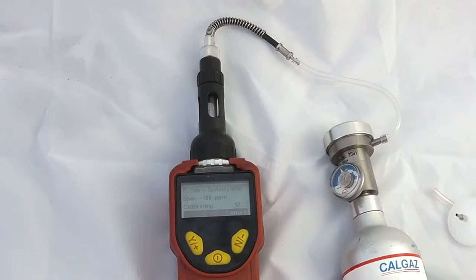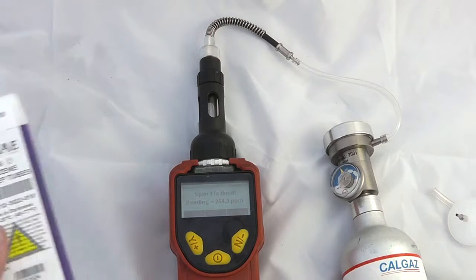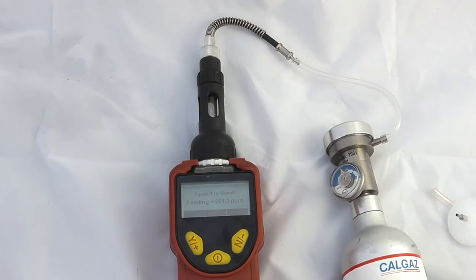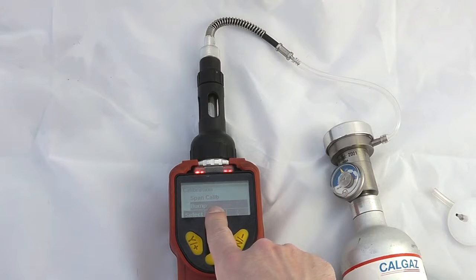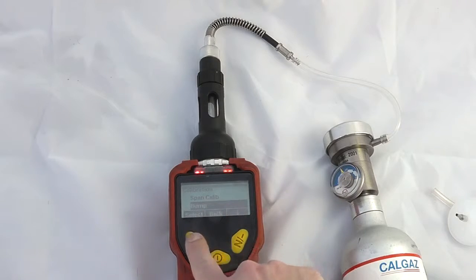At the end of this we should get a positive calibration reading for isobutylene. I would suggest if you are doing benzene measurements, you should use a can of benzene gas rather than isobutylene, and equally any calibrations that function with benzene should be done using a RAE separation tube. So span 1 calibration is done. You can see at the moment it's reading pretty high, but we also get the option to bump test this particular device. This is particularly important on gases like benzene.